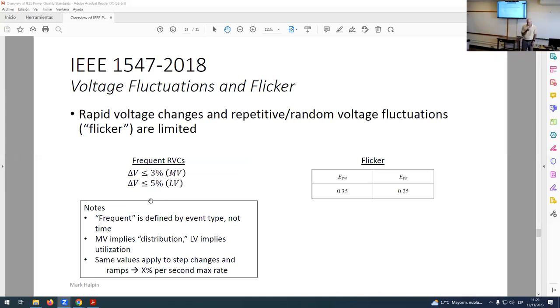From the perspective of voltage fluctuations and flicker, flicker limits are given in terms of Pst and Plt. Every generator interconnecting to our distribution system is allowed a flicker limit, a short-term severity limit, Pst, of 0.35, and a long-term flicker severity, Plt, limit of 0.25. Period, done. End of story. Is that what we should do? Probably not. Is that the best thing? Probably not. That's what it is today.